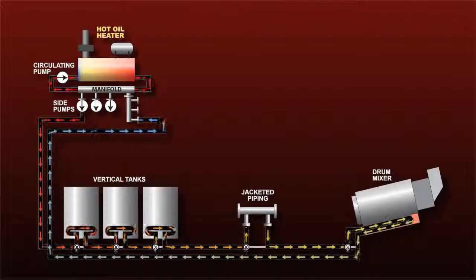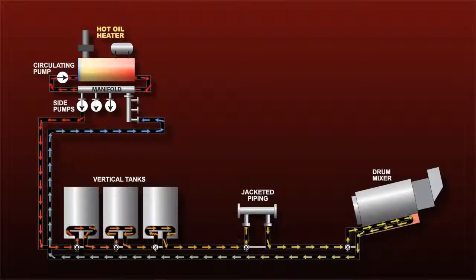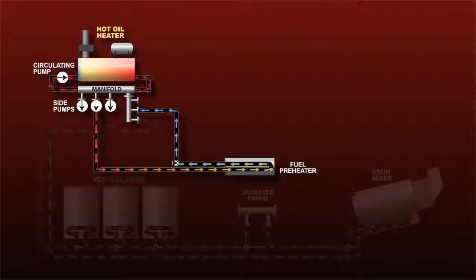Each outlet serves as the hot oil source for an independent circuit with its own side pump. Each side pump circulates the oil through a circuit with less resistance because it has fewer components.